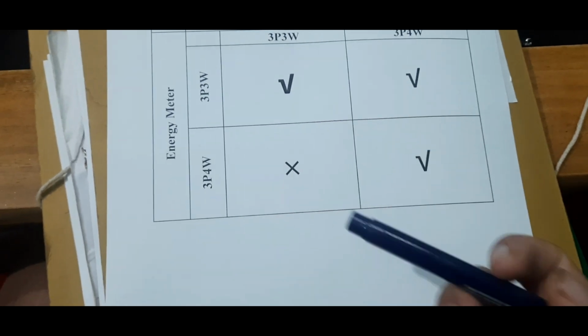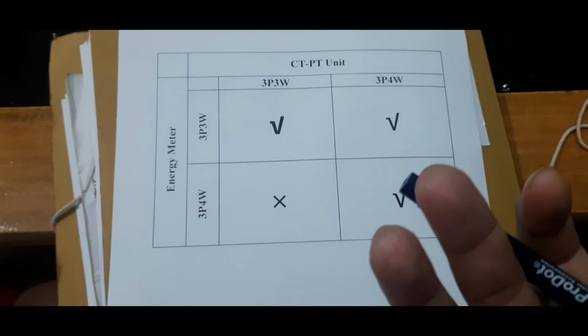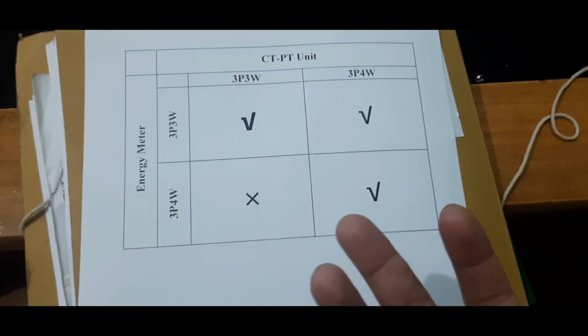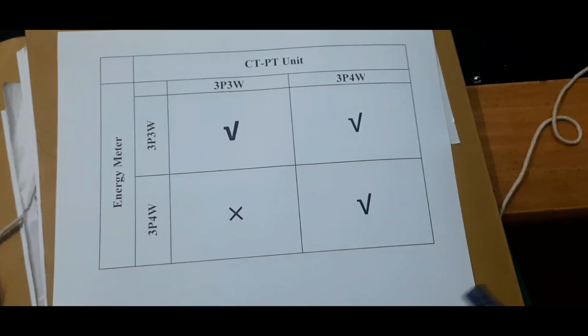And here we're using a three-phase, three-wire meter, just like our consumer, this green frame. Here the combined set or CTPT unit is three-phase, three-wire, which is why we cannot use the other. Three-phase, four-wire meters nowadays are all smart meters. We haven't used this for this particular consumer, because this is non-smart. Three-phase, three-wire meters are non-smart.